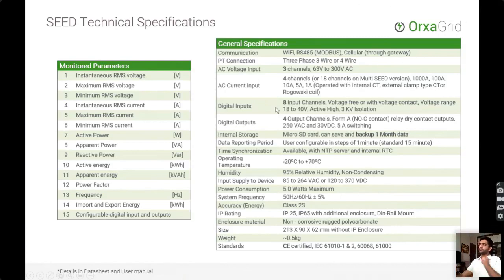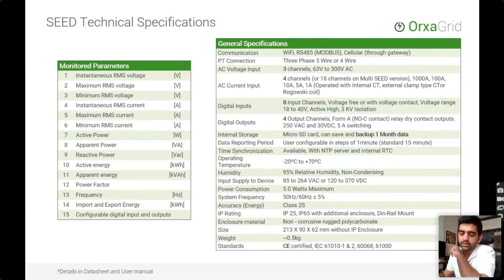Moving on, the device also has digital inputs and outputs, so to measure breaker status, isolator status, and so on. And you can also do remote controlling. So we provide 4 channels for remote controlling of each feeder. This can be used for operating your breaker and your isolators per feeder. The device comes with internal storage, a micro SD card. So it provides a 1-month backup data of the entire measurements, just like any energy meter. There's time synchronization also within the device, so individual feeders can be synchronized, and then you can understand at a wide area network the conditions of the entire network that is being monitored. The device is also CE marked, CE certified, and provides accuracy of 0.2 class, as I mentioned before.